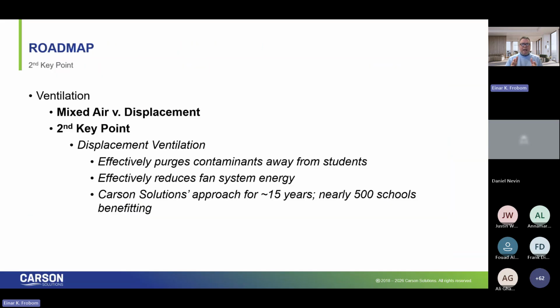So displacement, on the other hand, doesn't force air into the space. It slowly billows air in low near the floor, and then it effectively takes advantage of the body heat or the other heated sources in the space that increase the temperature of the air around the person and increase the buoyancy, and that air travels directly up a tight thermal plume to people's breathing environment. And there is no localized energy usage. There is no fan power connected load in the space for these diffusers.